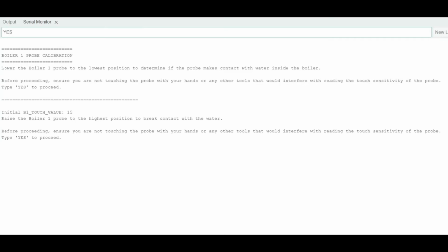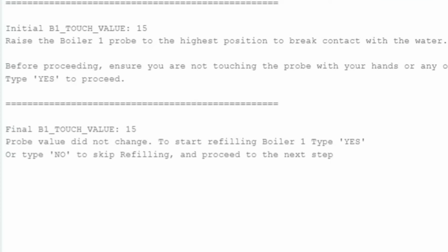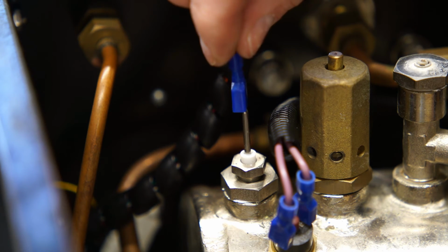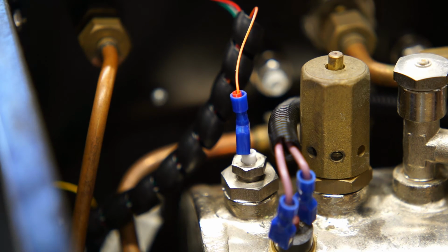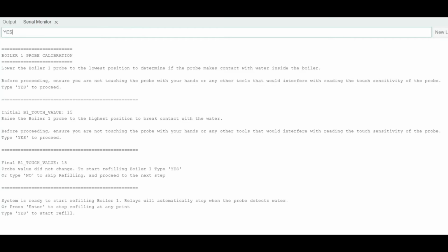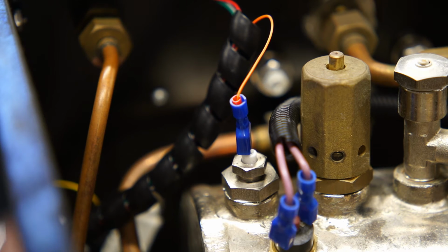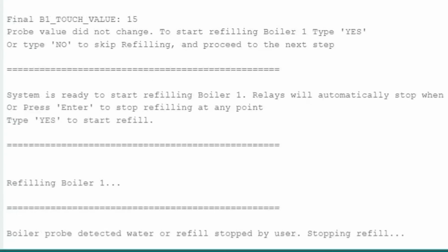Then I reply with yes to proceed. The wizard has not detected any change with the probe and asks me if I would like to refill the boiler, which I respond to with yes. Next, I set the probe at my desired fill height and type yes to start refilling. The pump will automatically stop when it detects water is touching the probe.